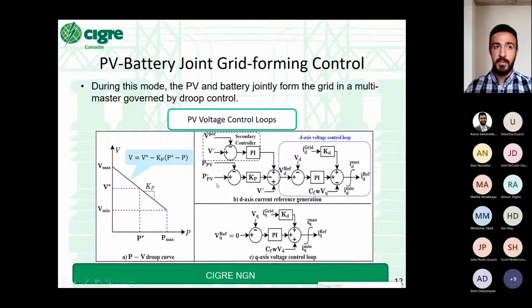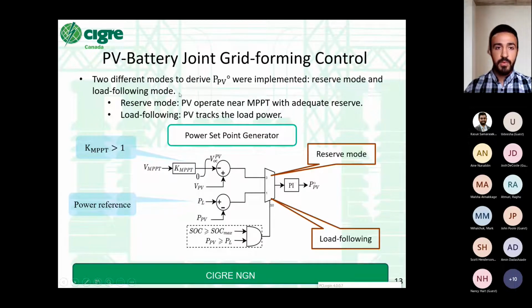However, when we operate the PV VSCs in a droop mode, it would be inefficient, as the main concern is to harness the maximum available power. Therefore, there are two different modes to derive the set point of the PV. These two different modes are reserve mode, such that the PV will operate near MPPT with an adequate reserve. And this reserve is going to facilitate forming the voltage and the frequency, which is very crucial when you operate a PV VSC in a grid forming.